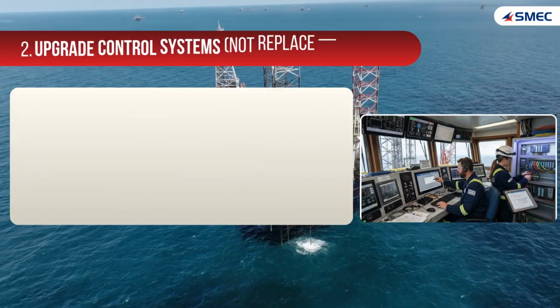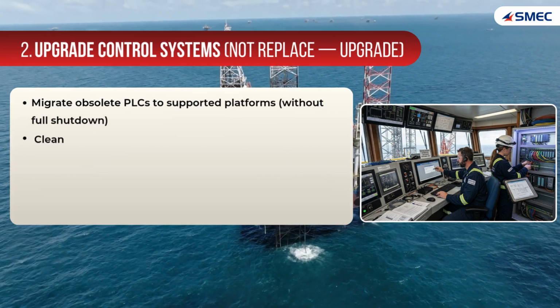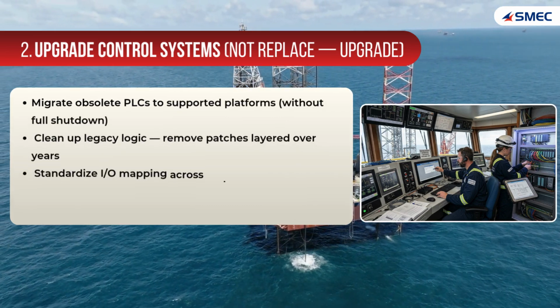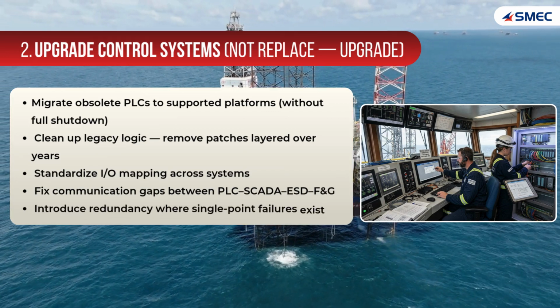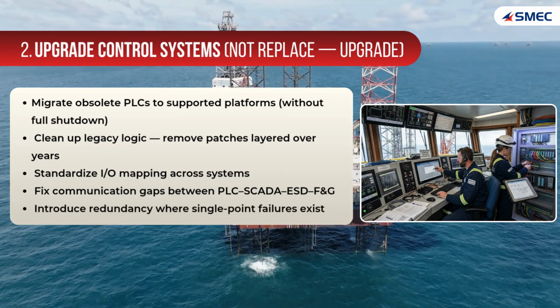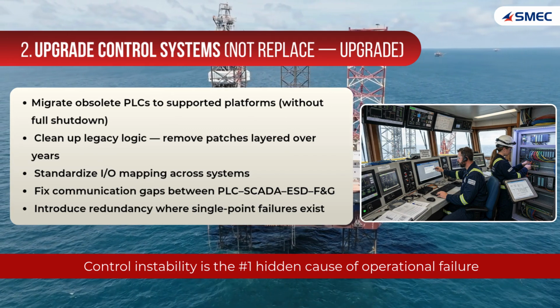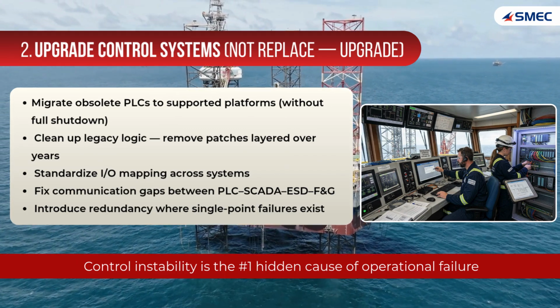Second, upgrade the brain. You don't need a total shutdown to migrate obsolete PLCs. Clean up the patchwork logic that's accumulated over decades. Eliminate the gaps between PLC, SCADA, and ESD systems to remove single-point failures.